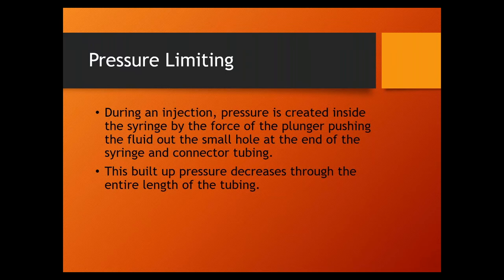The pressure limit is to keep the syringe from rupturing during the injection - it is patient safety, but not about keeping pressure away from the patient directly. Things that affect how much pressure builds up: flow rate is 99% of it - the faster the injection, the more pressure. Other factors include viscosity of the fluid (contrast is slightly thicker than water, and some contrast fluids are thicker than others), and the length and diameter of the tubing and needle. The thinner the tubing or needle, the more pressure builds up.